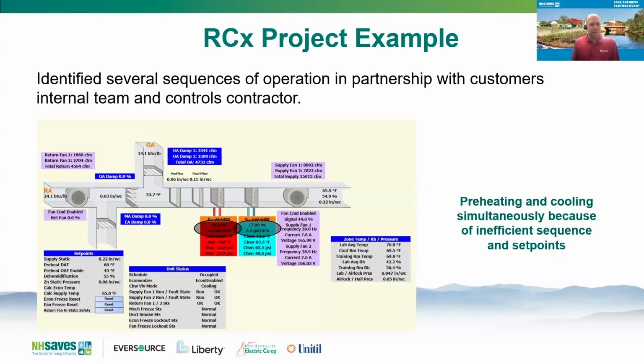Here's a graphic of one of the air handlers. We identified several sequences of operation in partnership with the energy manager and their controls contractor. Here was an example of preheating and cooling simultaneously because of inefficient sequences and set points. They were literally running the heating coil and the cooling coil simultaneously when it was obviously not necessary to do so.